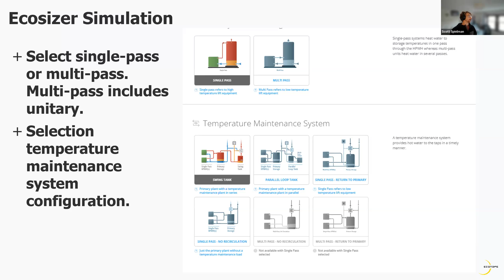Then you'd select the system type—either single-pass or multi-pass—and the temperature maintenance system configuration, which defines how the recirculation is piped. These align with the standard configurations defined in the Northwest Energy Efficiency Alliance Advanced Water Heating Specification, which is also referenced in Title 24 and recognized as best practice for installing and setting up heat pump water heating systems.